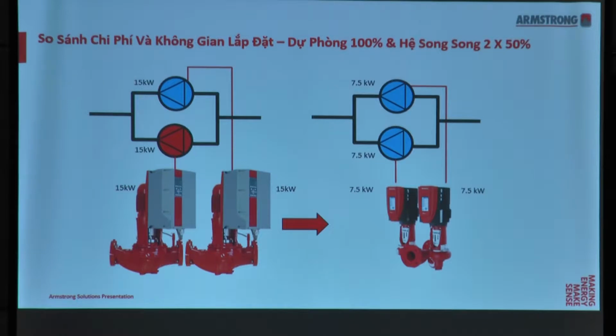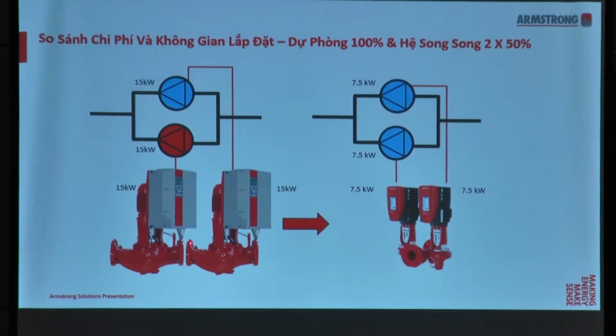Okay, now we'll talk about carbon footprint or space savings. So now we're talking about, again, duty standby versus a parallel pump. And what we've done is just to compare, right? We know that most of the time we are using an end suction or a horizontal split case. So when you use a vertical inline, you will know there is actually much savings. Right now what we're trying to illustrate is that we're going to use vertical inline and compare it against our tango pumps. Okay? So you realize that our horsepower has reduced, right? And the sizing has also reduced greatly.